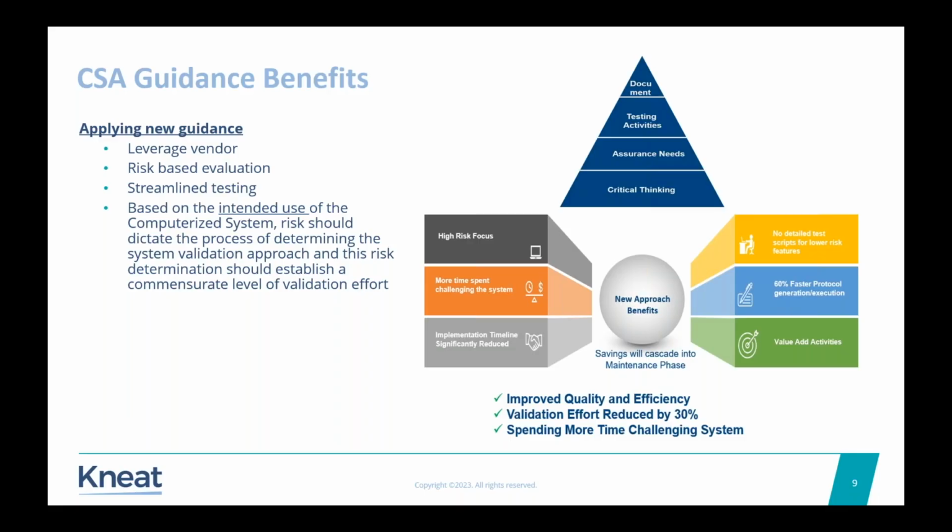Again, I've got a user manual. Do I need a 10-page test script to show the user manual is correct? I probably don't, because it's low risk. It's not going to impact the patient. It's not going to impact the quality. Let's test at the appropriate level.